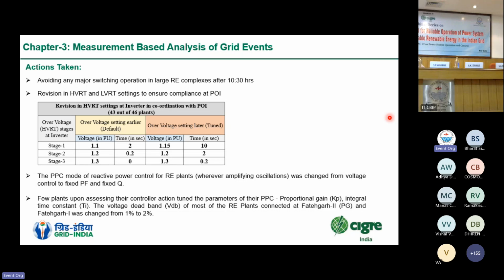Another part which we did was we took up the issue of HVRT and LVRT settings, and we arrived at a conclusion that the plants were not able to observe the low voltage ride through and high voltage ride through. They were not able to sustain their operations because there were some differences in the opinion between the plants and what regulations direct them. Regulations desire plants to carry out the ride through based on the voltage at the point of interconnection. But the plants have implemented the settings of the low voltage ride through and high voltage ride through based on the voltage at the inverter terminals.